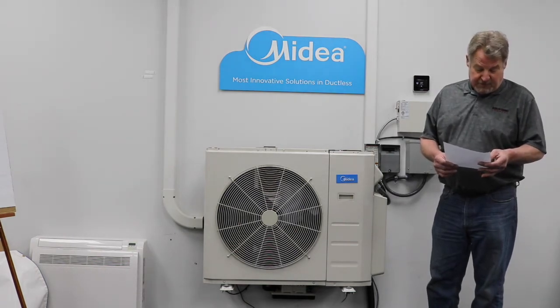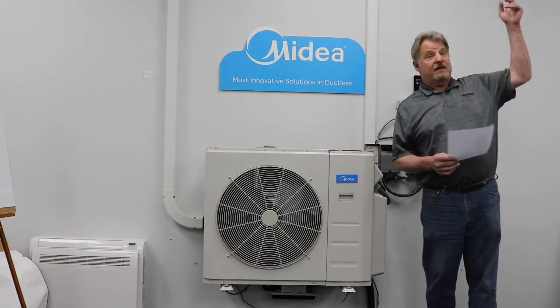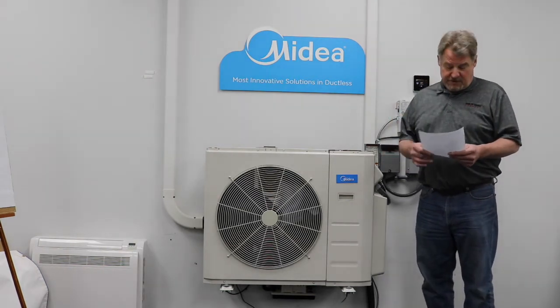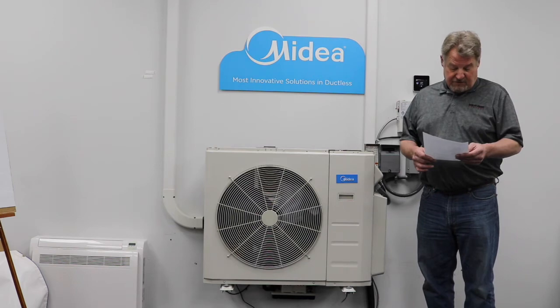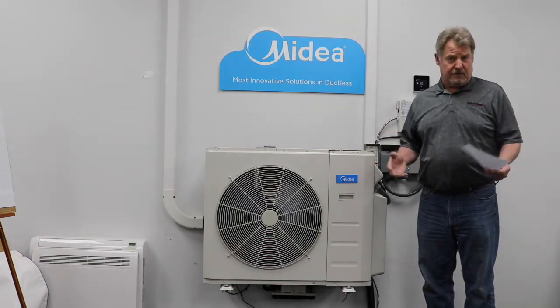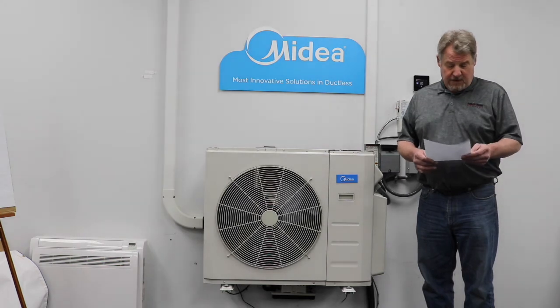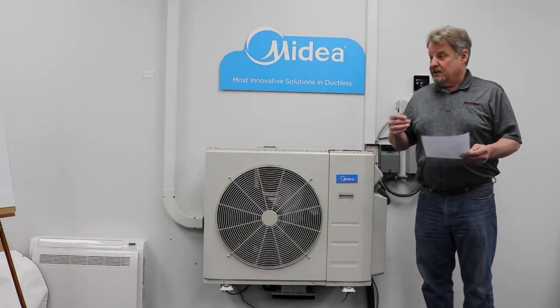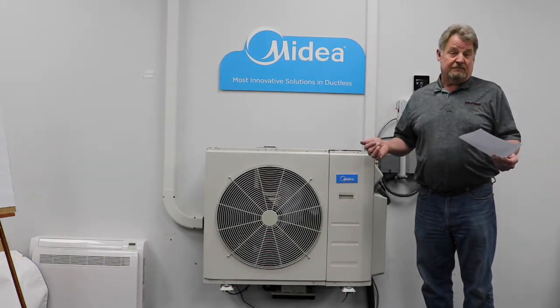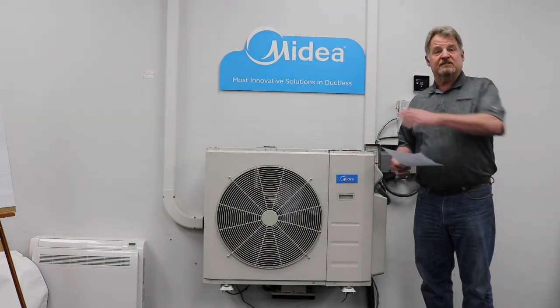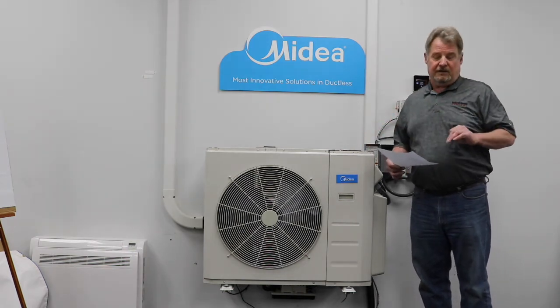Then I can go down from 22 to 26 and read all of the return air sensors, so in my fan coils, I can read the return air sensors. And if I go from 27 to 31, it's going to read all the evaporator temperature sensors. What's kind of cool about this is if we think we have a sensor out of calibration, I can simply look and see what each sensor is reading.